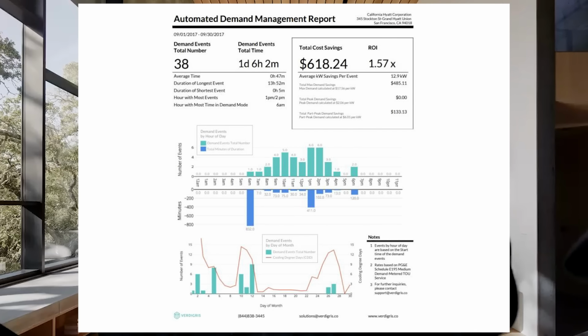One of the earliest use cases of our sensor technology was managing when that peak is going to happen. We built an algorithm that forecasts where those peaks are. Every time we saw a peak was about to happen, we would take an action - come in, tell the building management system or the HVAC system or the engineer to come down and change these set points. Every time we did that, we tracked the performance delta from what the forecast said.